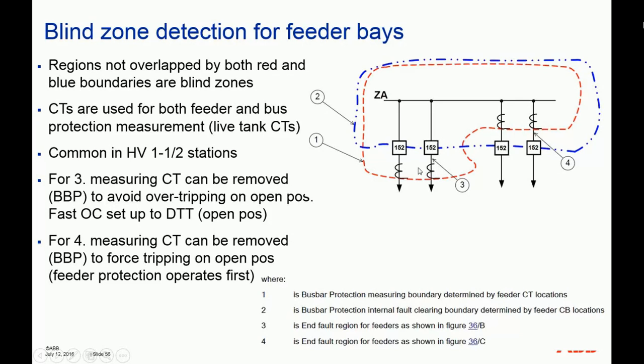So in this case, what you can do, once the breaker is open, to avoid over tripping on open positions, is set up a fast overcurrent relay, say an instantaneous overcurrent relay, that is enabled when the breaker is open. In that case, when it detects still current flow, it will send a direct transfer trip or any type of communication assisted tripping to open the breaker at the remote end. In that case, you can completely isolate the fault.